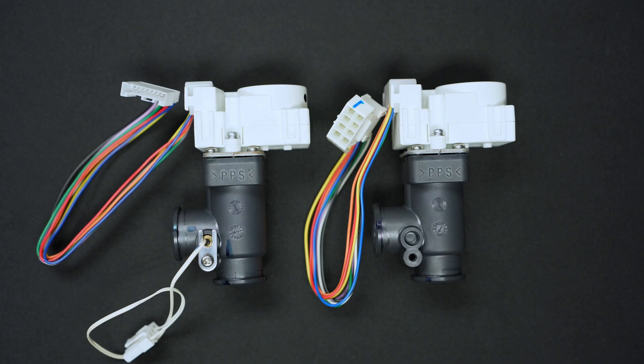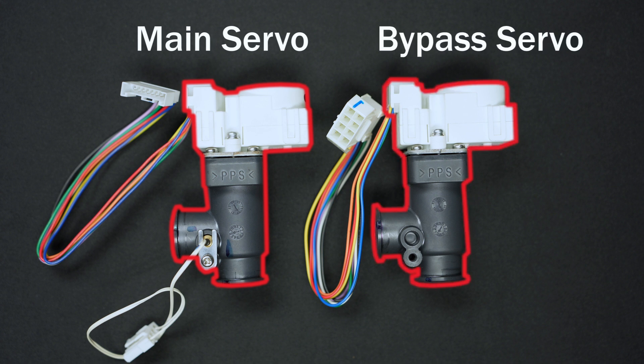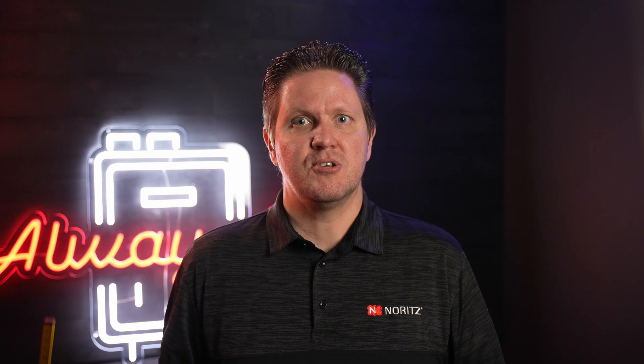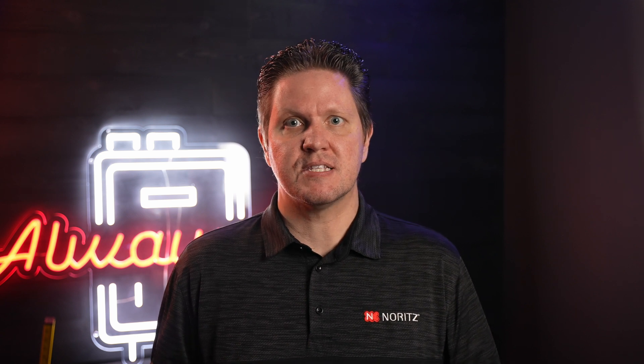All Noritz units, large and small, will have a main servo which controls the total flow that can pass through the unit. Larger units will have an additional bypass servo which allows a certain amount of water to bypass the heating process and mix with the hot water leaving the heat exchanger. The bypass servo allows for additional control and safety of the hot water output temperatures. The two servos work together to ensure the heater will always produce the set temperature regardless of demand and maintain the industry's best temperature stability.